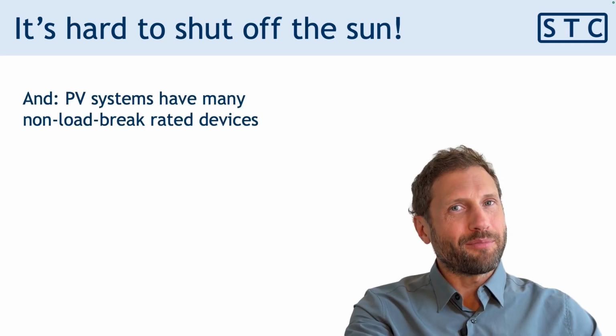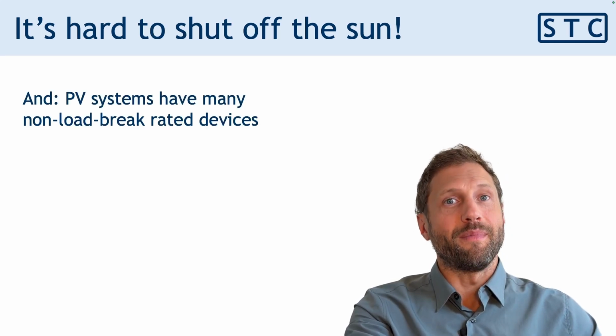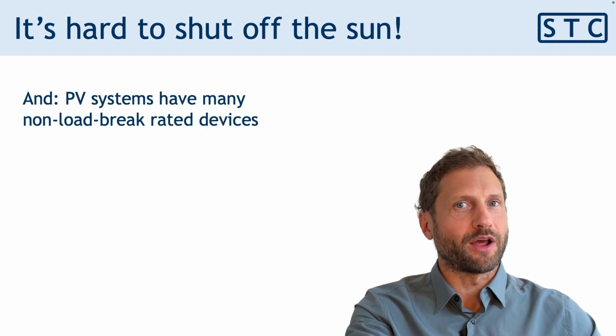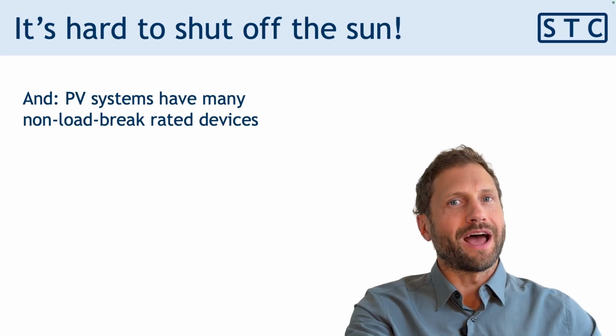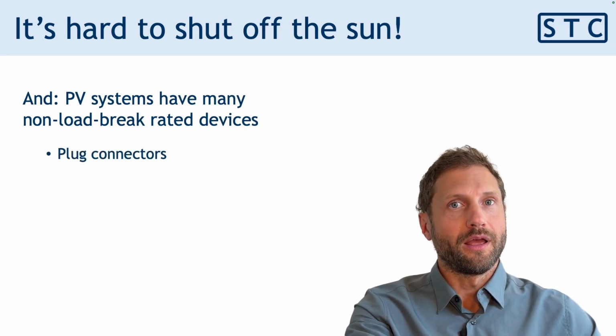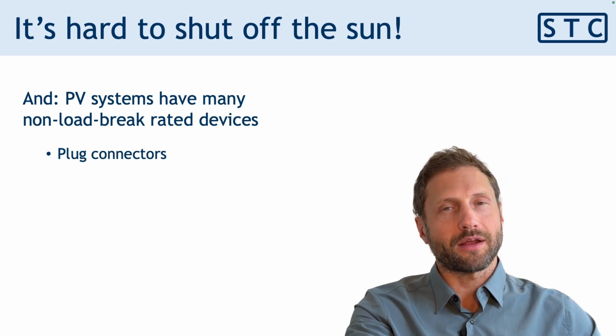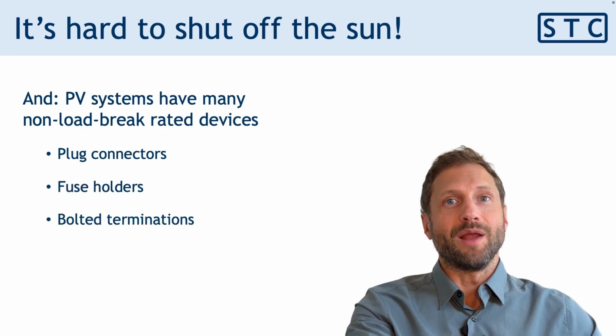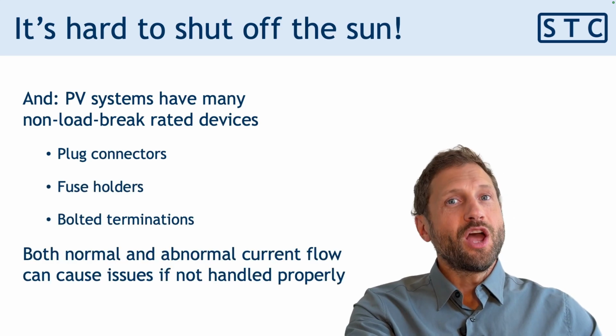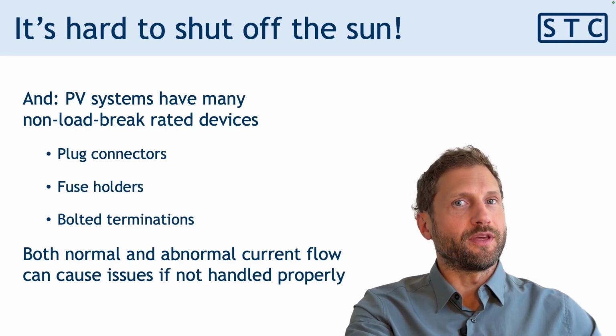And this can be a problem because PV systems have many non-load break rated devices. These are devices that are not intended to be opened or operated while there's current flowing. Some examples include plug connectors, fuse holders, and bolted terminations. Both abnormal and normal current flow can cause issues with these devices if they're not handled properly.